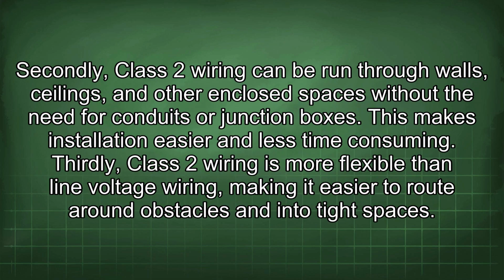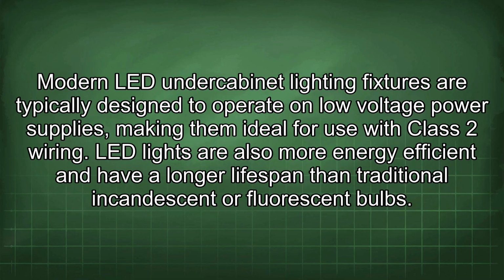Secondly, Class 2 wiring can be run through walls, ceilings, and other enclosed spaces without the need for conduits or junction boxes. This makes installation easier and less time-consuming. Thirdly, Class 2 wiring is more flexible than line voltage wiring, making it easier to route around obstacles and into tight spaces. Modern LED under-cabinet lighting fixtures are typically designed to operate on low-voltage power supplies, making them ideal for use with Class 2 wiring.